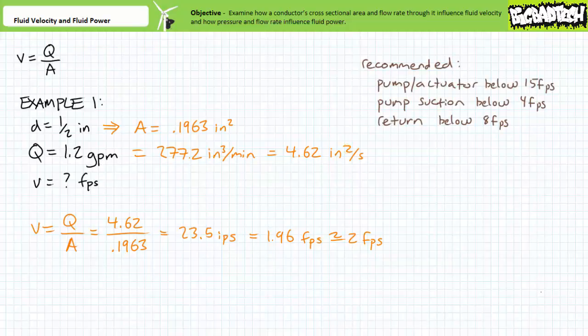Depending upon the application, most manufacturers recommend keeping fluid velocity below 15 feet per second between a pump and an actuator, below 4 feet per second in a pump suction line, and below 8 feet per second in a return line. This explains why suction and return lines are often larger in diameter than working lines — to keep fluid velocity below these figures.